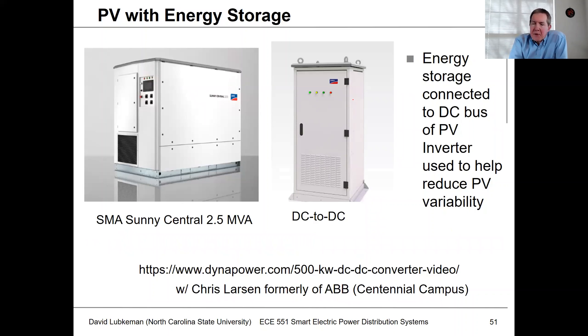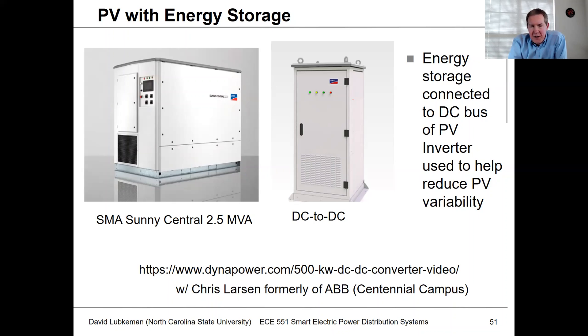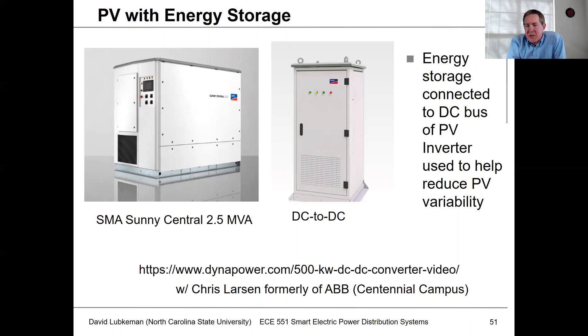In the future, we're likely to see new PV sites combined with energy storage. There's a lot that energy storage can do to make large-scale PV easier to integrate. You'll see solutions where storage is integrated into the DC bus of the PV inverter — the reason being that the utility only sees one inverter interface. Separate energy storage would require working through two inverter connections in the interconnection procedure.